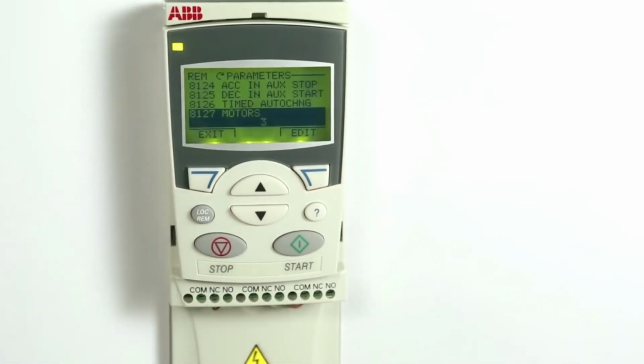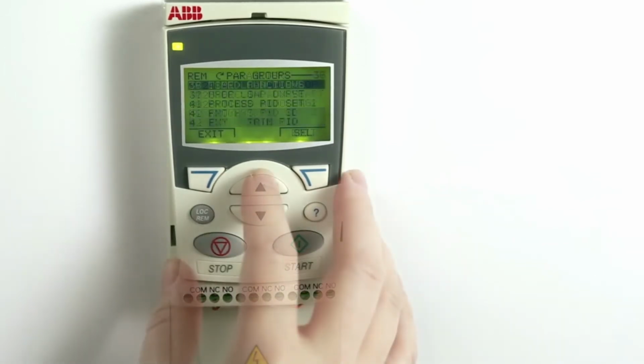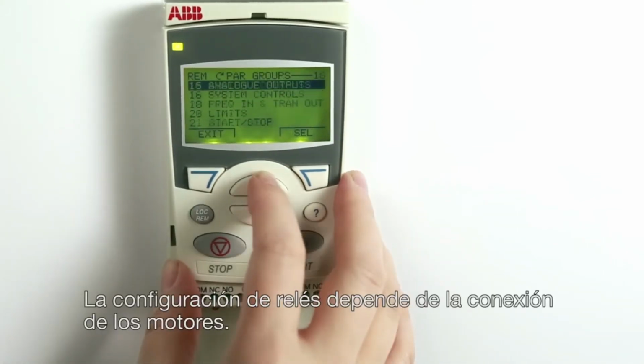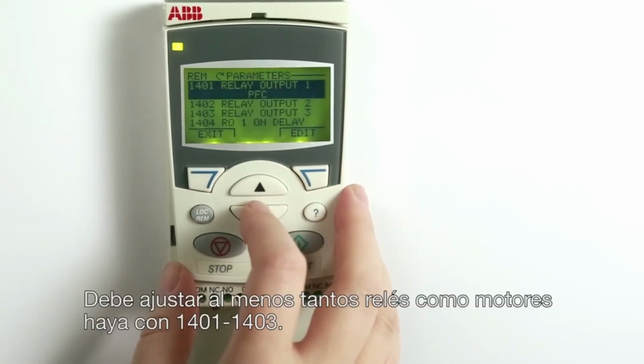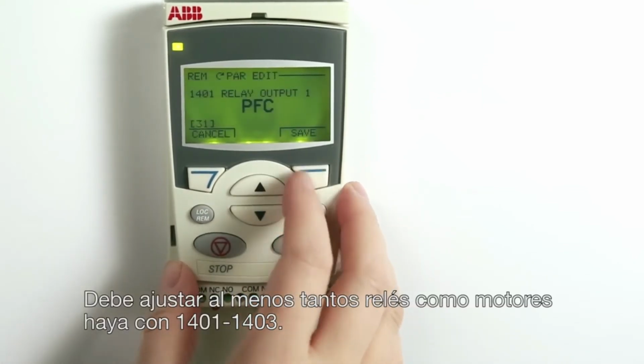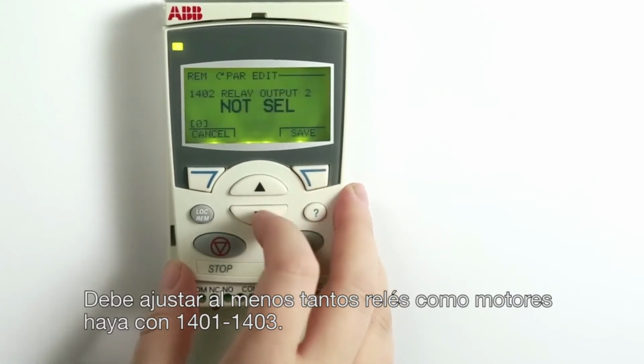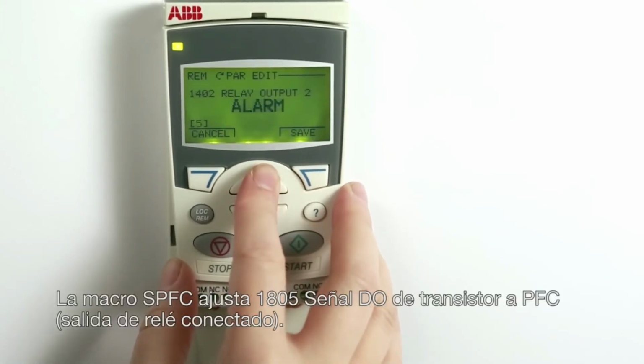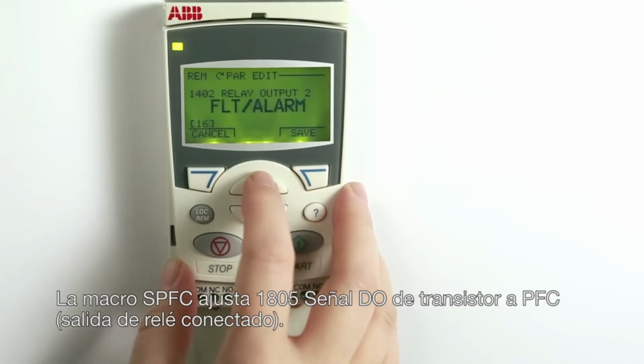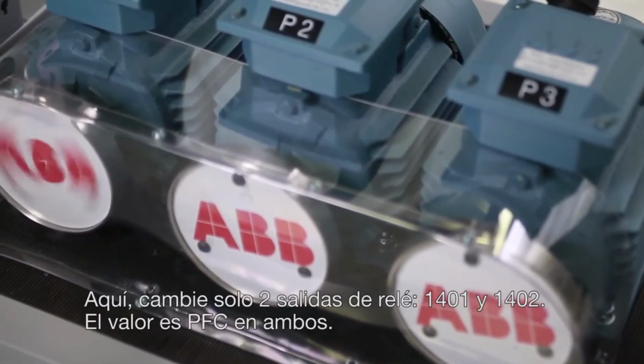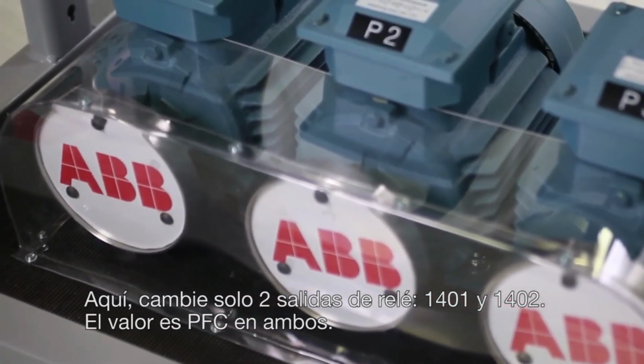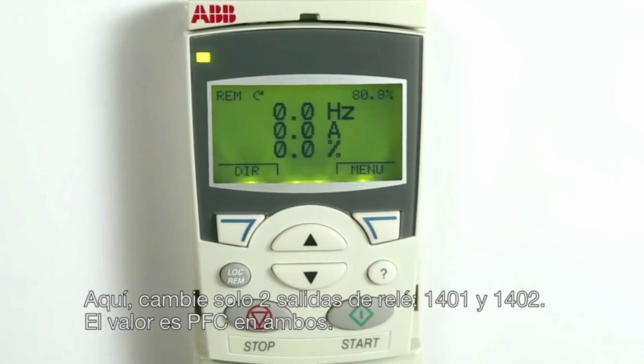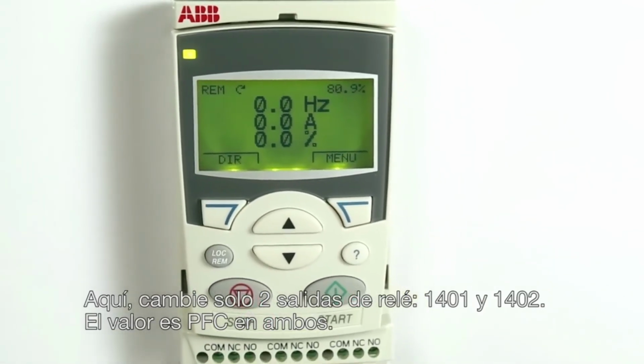Then press Exit. Then go to group 14 Relay Outputs. Relay configuration depends on how the motors are connected. We must set at least as many relays as there are motors with parameters 1401 to 1403. The macro SPFC already sets transistor output parameter 1805 DO signal to PFC as an additional relay output which is connected. So in this case, we change only two relay outputs, 1401 and 1402. The value is in both PFC.